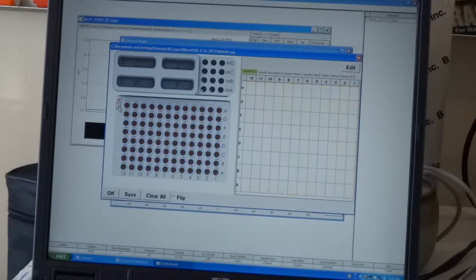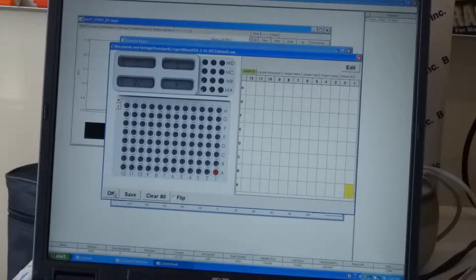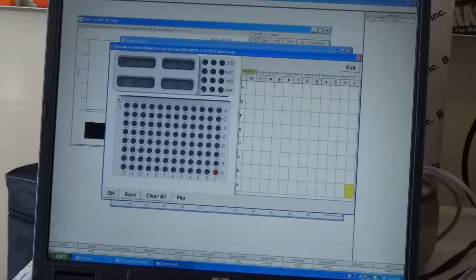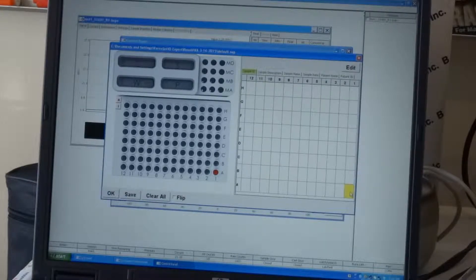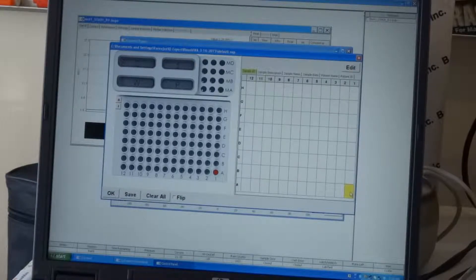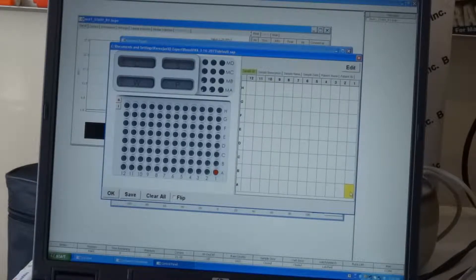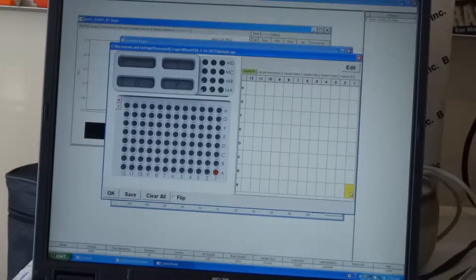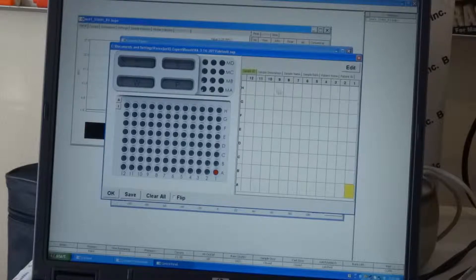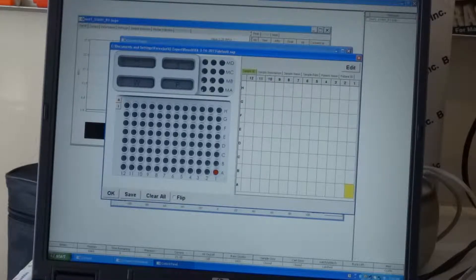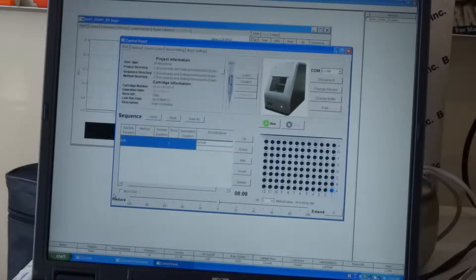So again, we select A1 and we say OK. And also, you have a table here, which you basically enter the name of each sample position. Or, you can export or import from your Excel spreadsheet into this table all the 96-well sample names. And the software will recognize it.